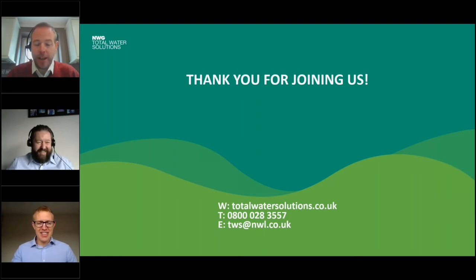Yes, is the honest answer. You can see Matt Morse's comments from the Legionella Control Association. So it is absolutely fine. They're calibrated to within plus or minus a couple of degrees, which to be honest isn't far off the standard temperature probes. I was at an install yesterday watching the chaps do that. The probes are foil wrapped around the pipe, and there's an algorithm that depends on what the pipe is. If it's copper or plastic, it works out what the right temperature is.